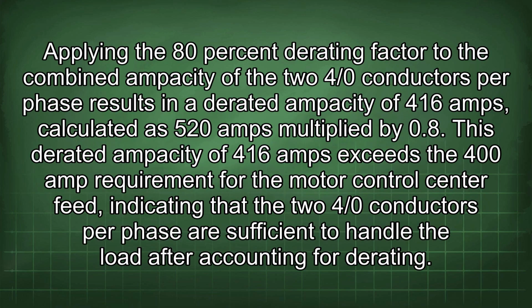Applying the 80% derating factor to the combined ampacity of the two 4/0 conductors per phase results in a derated ampacity of 416 amps, calculated as 520 amps multiplied by 0.8. This derated ampacity of 416 amps exceeds the 400 amp requirement for the motor control center feed, indicating that the two 4/0 conductors per phase are sufficient to handle the load after accounting for derating.